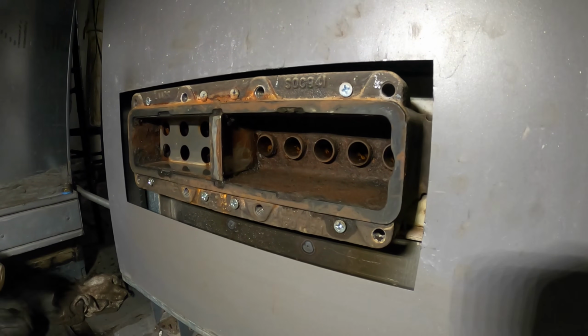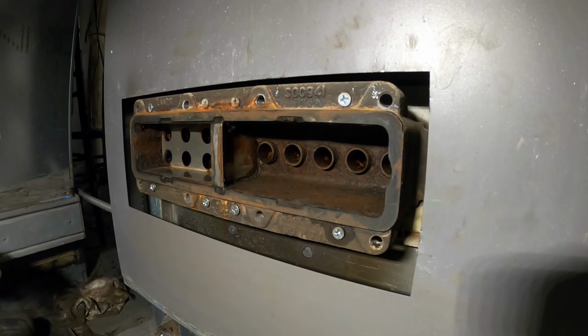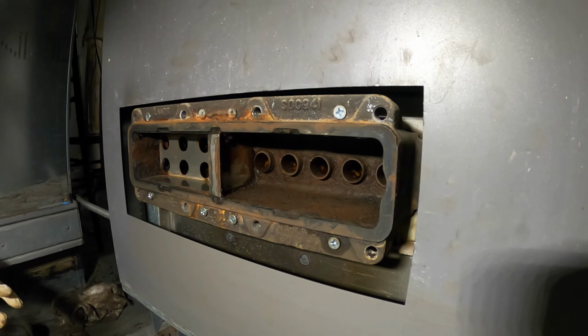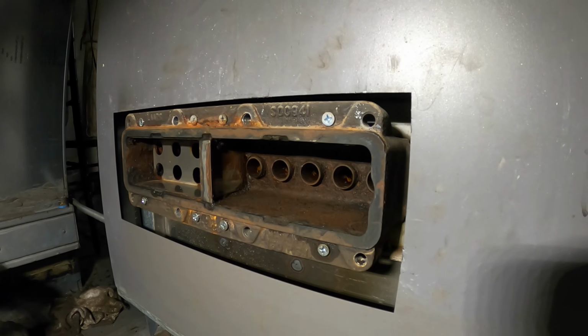That's a beautiful thing. Let's start with the next boiler. Let's turn it off, close the supply and return valves, drain it, and take it apart. We're gonna shut this boiler down. Look at this, I was deciding which one to take down. The other one, the pump sounds horrible. This one's pump sounds a lot better, but look at that, 1, 2, 3, 4.